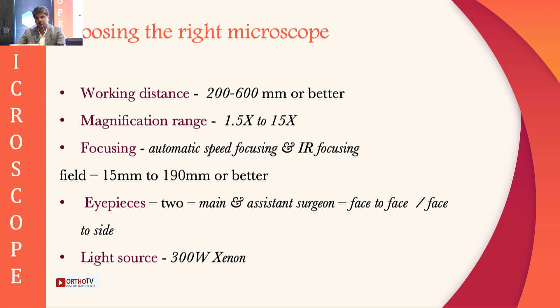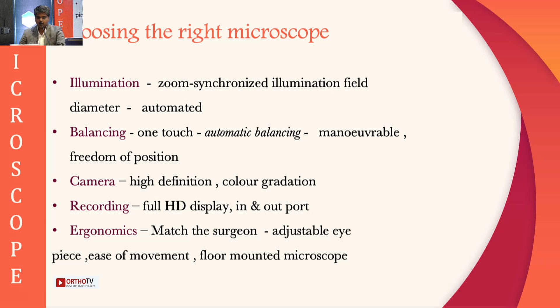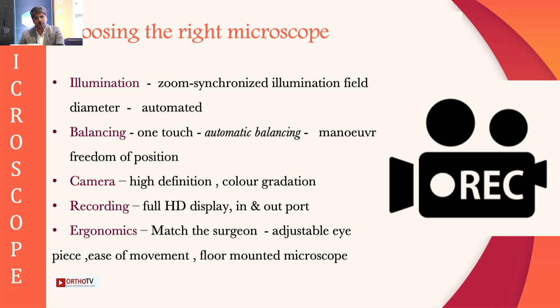Light source: xenon is better than halogen because it produces a visible spectrum of tissue to light. So illumination is one important thing. Illumination is what is required. So always choose an automated illumination which is related to your focus, again controlled by hand. Balancing: all microscopes should be balanced before your surgery, and the freedom of position comes. Camera: again, a high definition medical grade camera. Recording should have input and output, and ergonomics.